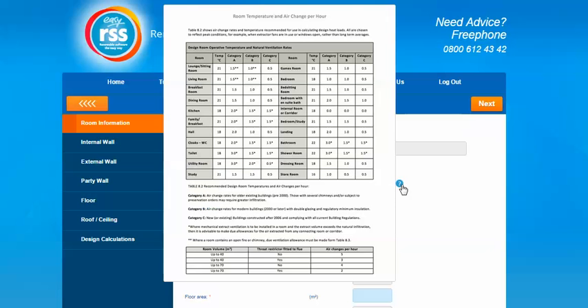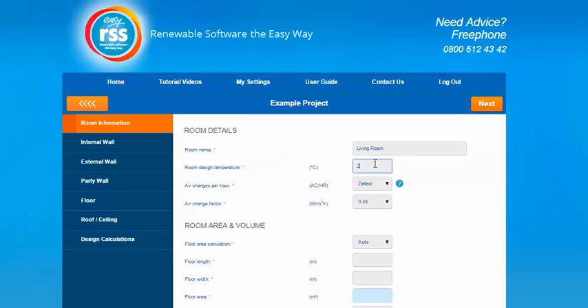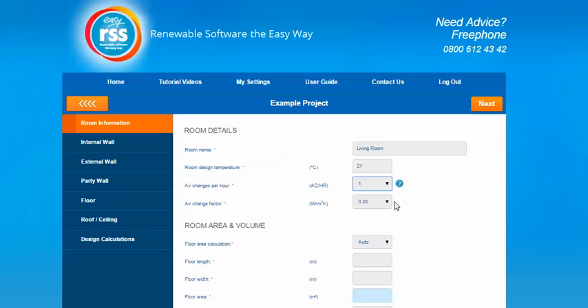For the next three options you can use the help icon. This table will give you the desired design room temperatures for each type of room and also the air change rate. There are three different categories for the air change rate and these are based on the age of the property. In our case we put 2003 to 2006, so category B would be the air change rate, and for the living room it'll be one. So we put 21 degrees in the room design temperature and an air change rate of one. The air change factor is a dropdown option giving you two options: 0.33 and 0.34. 0.34 is for properties built 2007 or onwards, so in most cases it'll be 0.33.